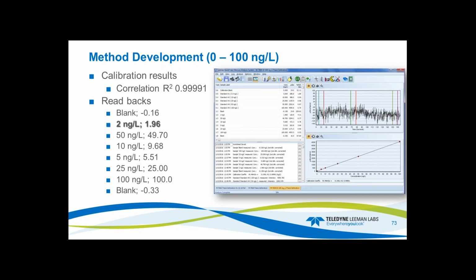The readback was 0.16. Now, the 2 nanogram per liter came in at 1.96. That is really good. Obviously, I remade it from the last one, so we have no contamination to show. The 50 is almost bang on, the 10 is great. Everything's well within acceptable ranges. For example, the 100 is 100.0, and then the second blank came in at 0.33. Look at the readbacks, the same thing.